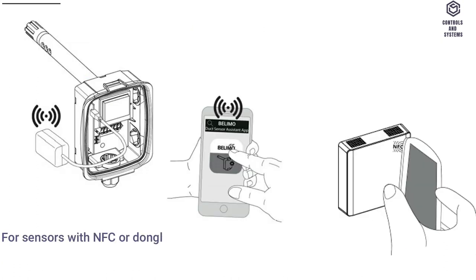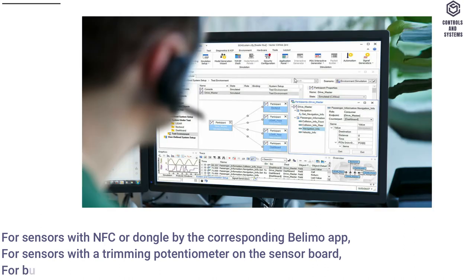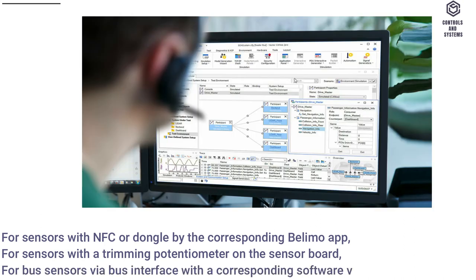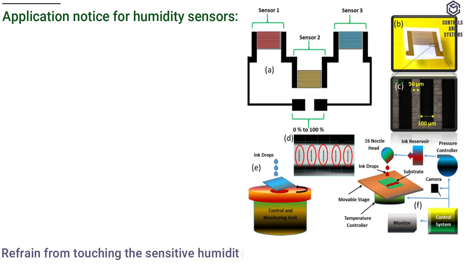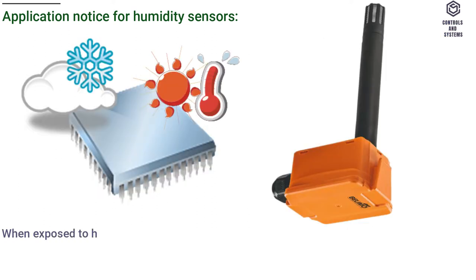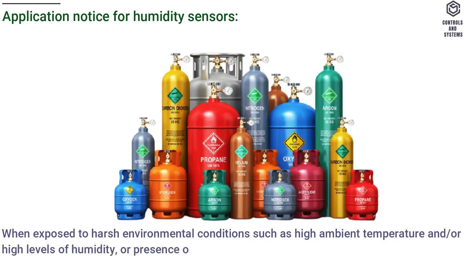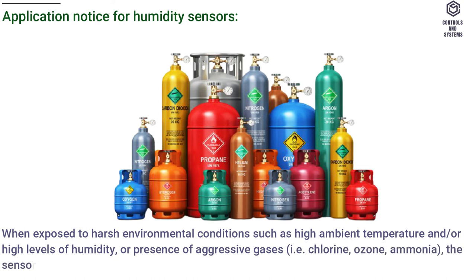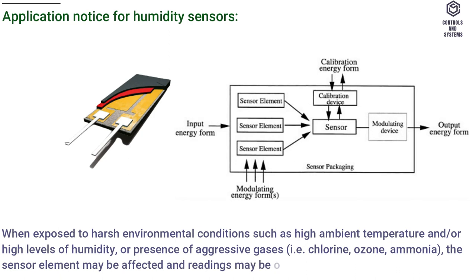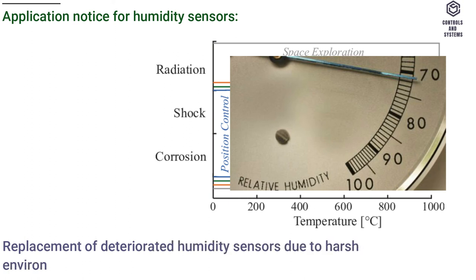Adjustment methods: for sensors with NFC or dongle, by the corresponding Belimo app; for sensors with a trimming potentiometer on the sensor board; for bus sensors via bus interface with a corresponding software variable. Application notice for humidity sensors: refrain from touching the sensitive humidity sensor element — touching the sensitive surface will void warranty. When exposed to harsh environmental conditions such as high ambient temperature and/or high levels of humidity, or presence of aggressive gases (chlorine, ozone, ammonia), the sensor element may be affected and readings may be outside the specified accuracy. Replacement of deteriorated humidity sensors due to harsh environmental conditions is not covered by the general warranty.